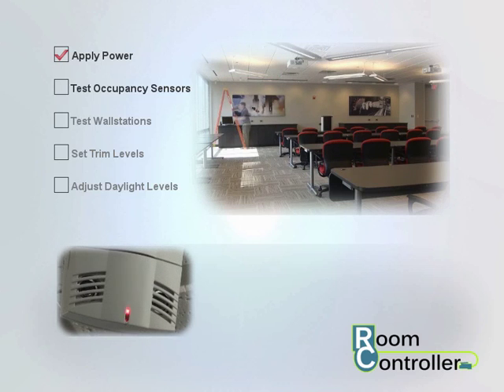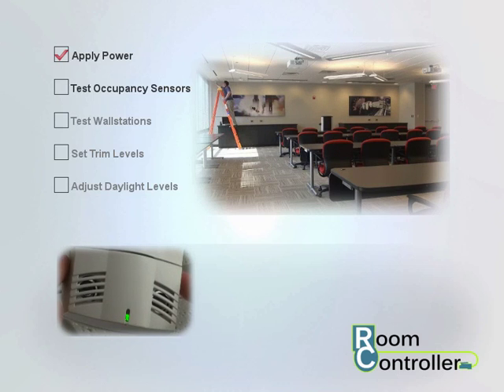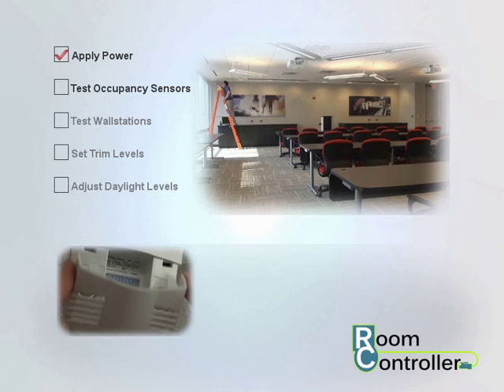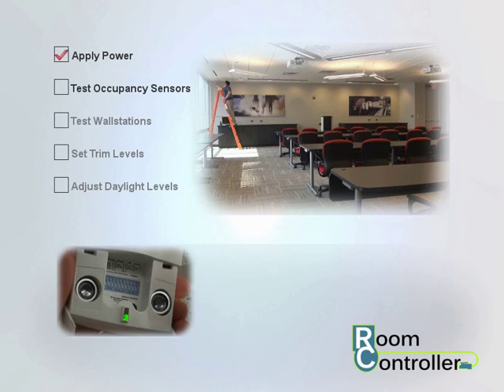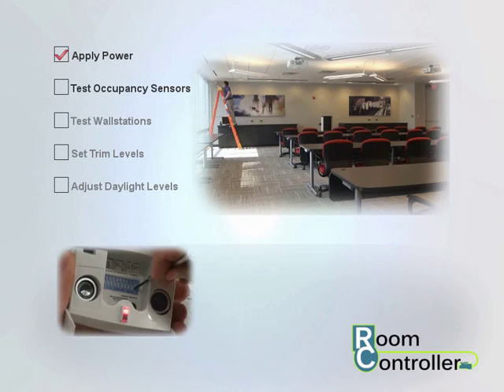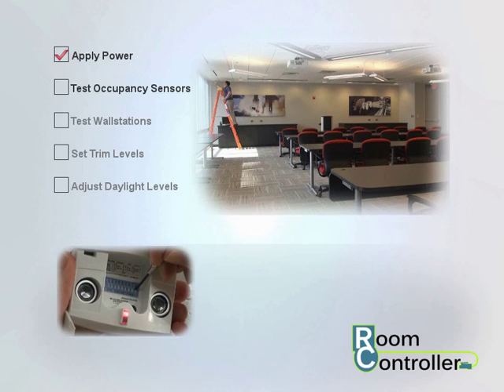After a short 2 minute power-up period, for OAC and OAWC sensors, move DIP switch 10 out of its current position for 3 seconds and then back to invoke test mode. If you have two sensors in your room, make sure both are in test mode.